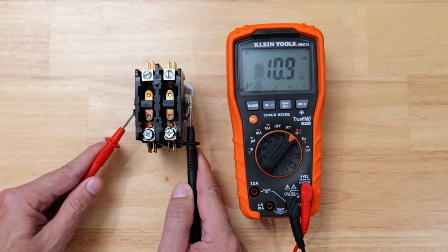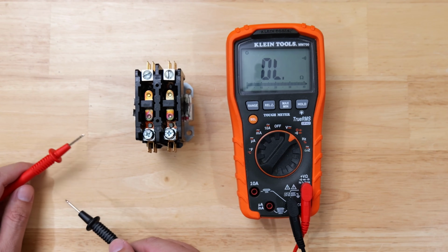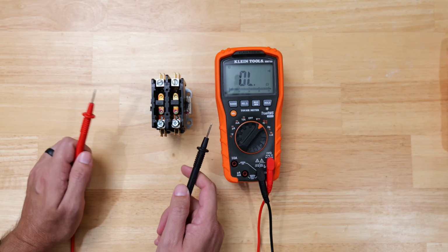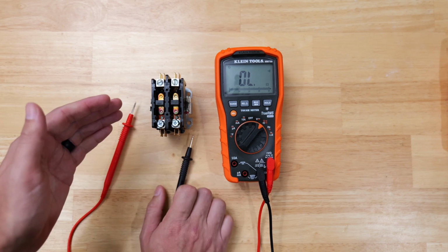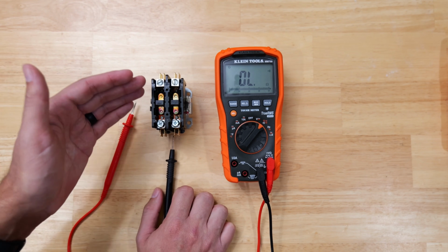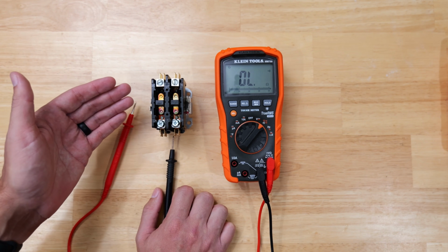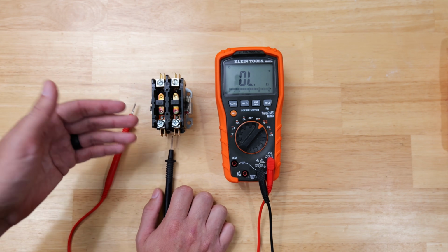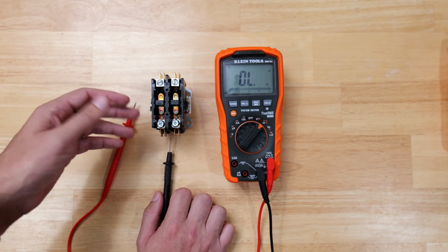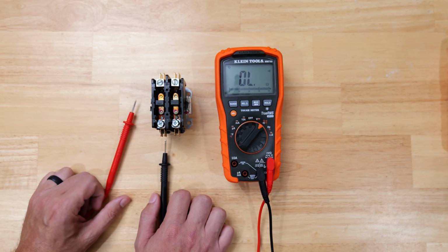That's where this test comes in handy. Whether you're testing an AC contactor, a water heater element, or something else, it can tell you if a part is still in good working condition. It'll let you know whether you need to replace it, or confirm that it's fine.